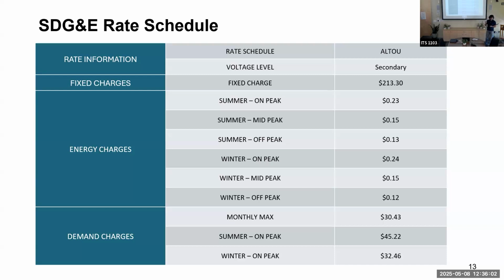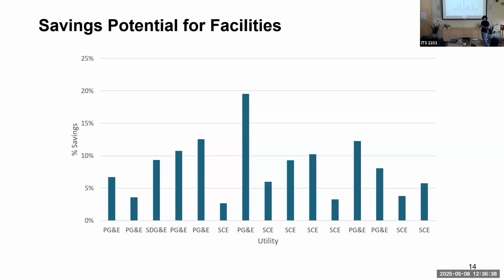So if your overall monthly demand lies in those on-peak periods between 4 to 9 sometime, you might be paying around $75 a kW. So the monthly max, you have to pay that whenever it occurs. But on top of that monthly max, you're also paying your summer or winter on-peak. And if you can reduce this on-peak demand charge, you can save $45 a kW. So for example, if you're reducing 100 kW from that on-peak period, you're reducing around $4,500 from your monthly bill each month. So this is the proposition for the facility.